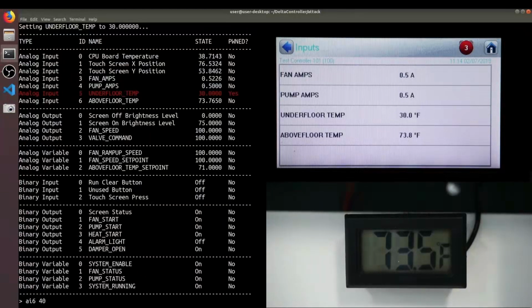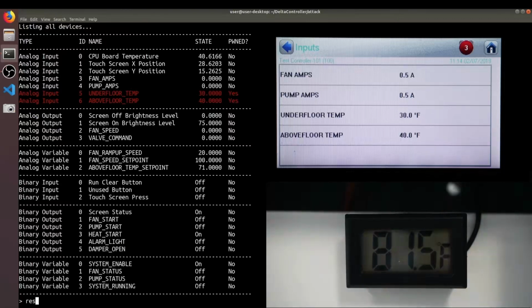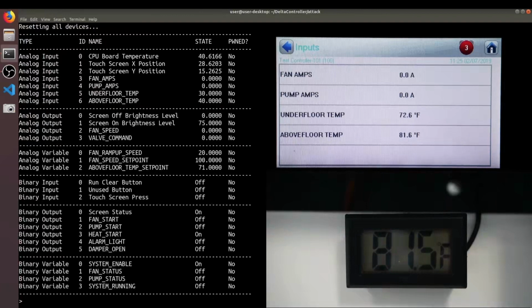The attacker changes what the system is reading for temperature, from the real temperature to 30 and 40 degrees respectively. What happens in your house if the HVAC system thinks it's 30 degrees in the room? It's not going to kick on, it's going to turn off. You can monitor our independent temperature system in the bottom right-hand corner, and the temperature in the data center starts to rise—with no alarms triggered, because the system thinks it's 30 degrees. Why would it trigger an alarm? Nothing appears to be going wrong.